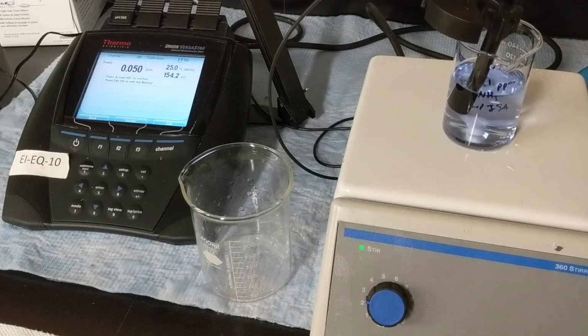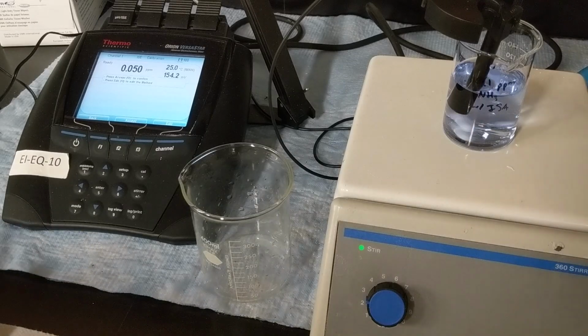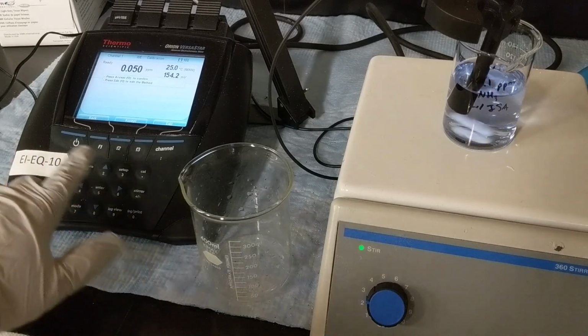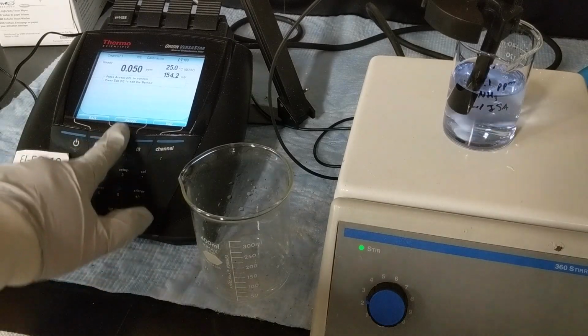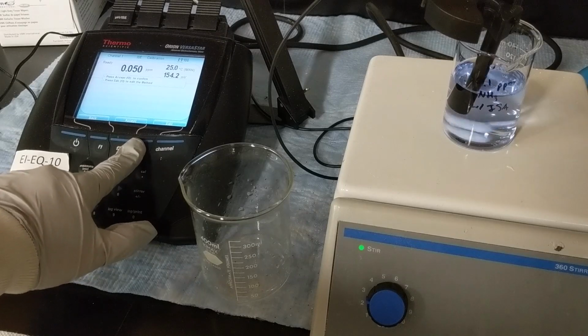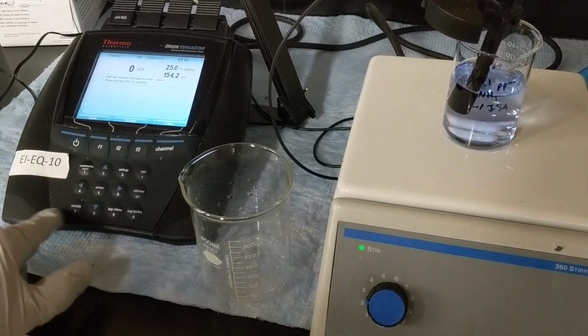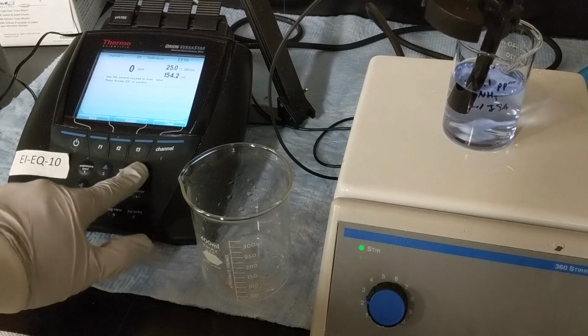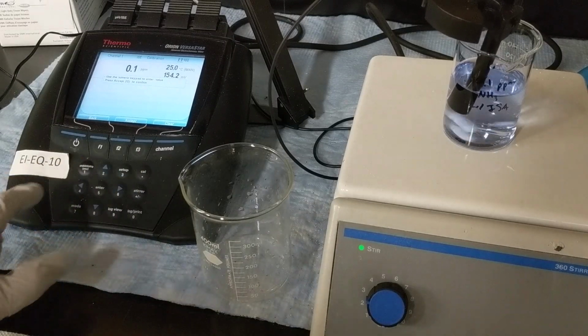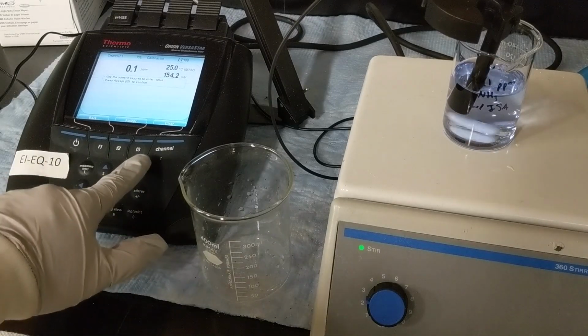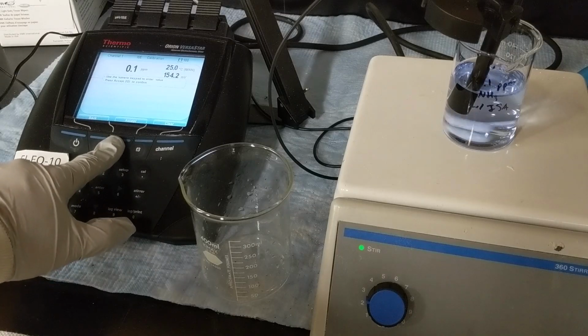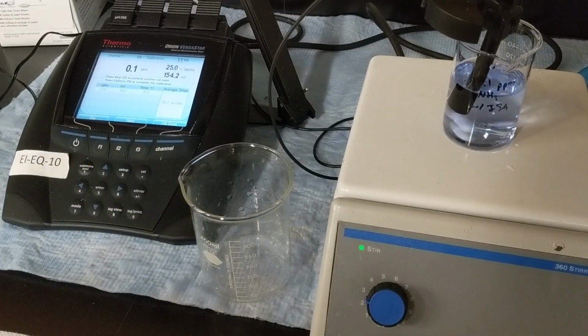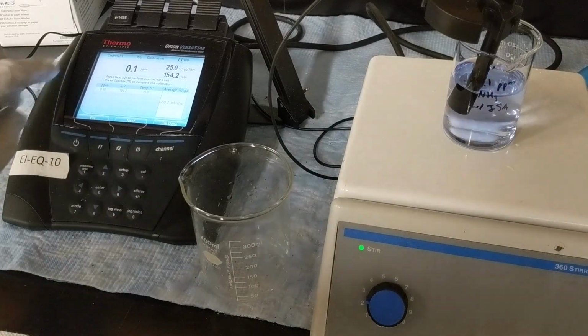So it has now stabilized at 0.050. It's given me that reading twice in a row. So now what I want to do is tell it this is actually a 0.1 part per million solution. So instead of hitting accept in the middle, I'm going to hit F3 for edit and tell it this is 0.1. And then F2 is accept. Okay, so now it has the first point.